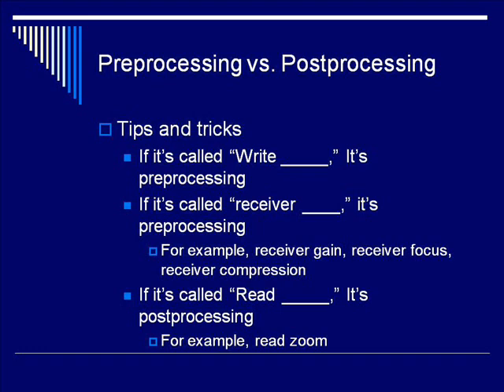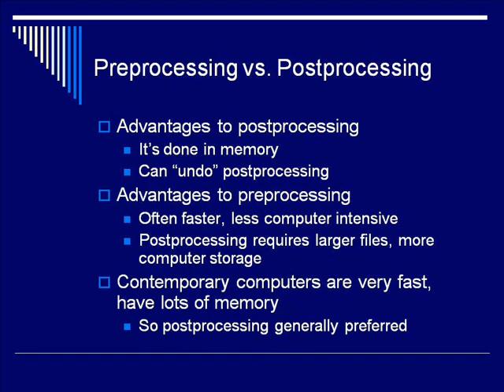For example, most machines have a read zoom option, which is post-processing. Why do something in pre-processing versus post-processing? Some things must be done in pre-processing before we have an image, and some things require an image and must be done in post-processing. But many things can be done either way. One advantage of post-processing is that it's done in memory, so we can undo it if needed. One advantage of pre-processing is that it's generally faster and less computer-intensive, since post-processing requires larger file sizes and more computer storage.